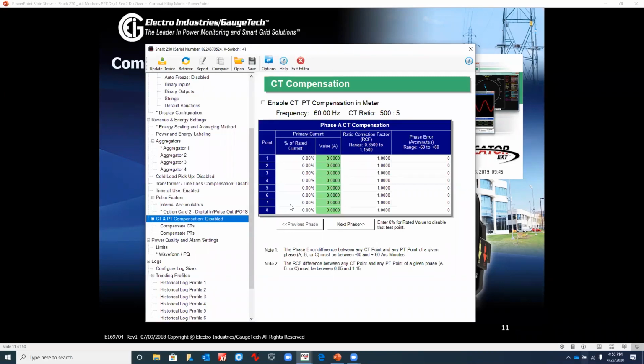CTPT compensation, those are errors in the instrument transformers that we will also discuss tomorrow. And basically, these are all driven by the transformer report. Someone tests the transformer and finds these inefficiencies, or I would say minor defects, which translate into a correction factor, and that would be inserted here. That's generally what you would retrieve from that.